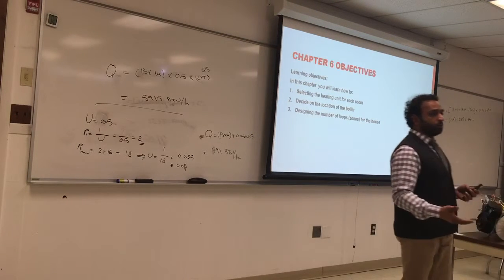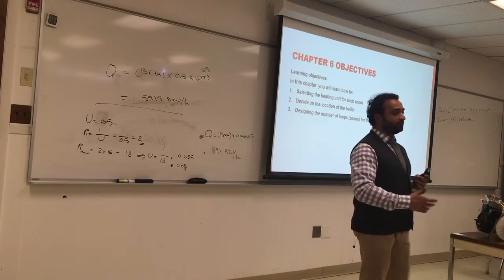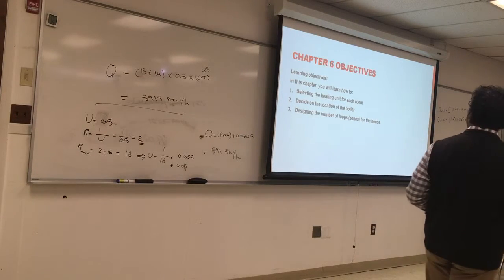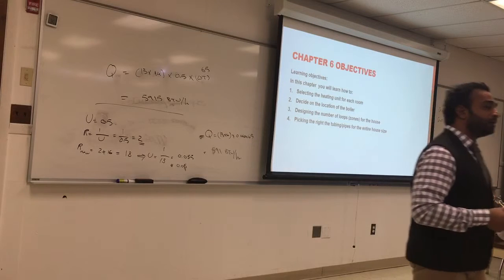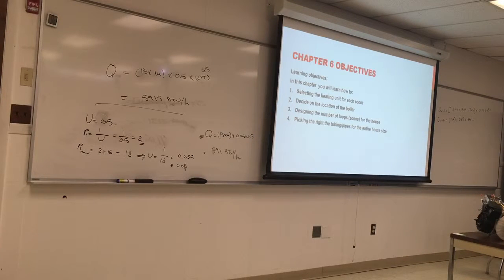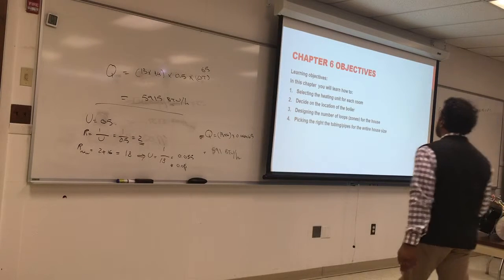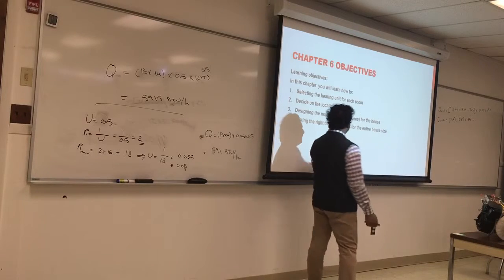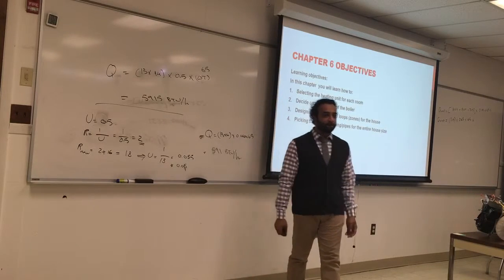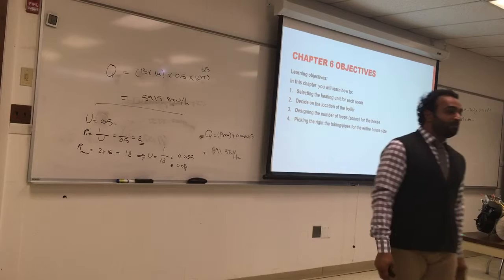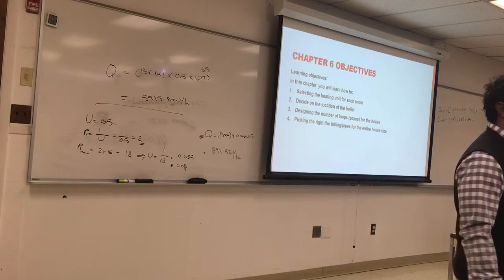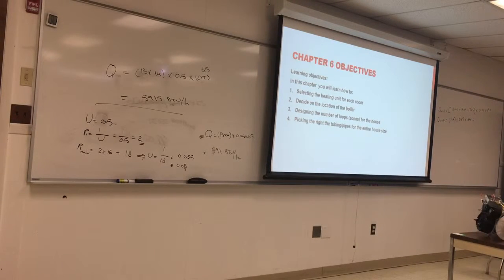And again, the more zones you have, the better, because that will have less heat in the house. So we'll talk about how to size the pump for each one of those zones, and what the heating requirement is. Picking the right tubing for the entire house size. So you want this pipe to be consistent. You want to reduce the amount of changing from large to small, small to large.